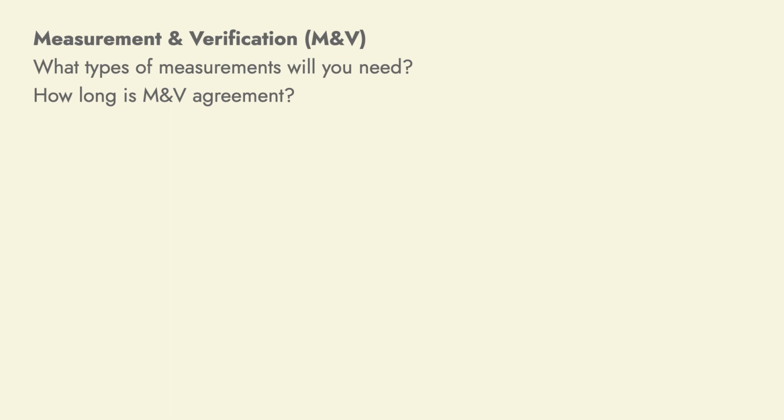Also, how long is that measurement and verification contract? Is it only for a year post-construction, or is it for more than that? 3, 5 years, 20 years, which is not uncommon for things like government buildings that have to guarantee that they are getting the savings that they were promised for a long period of time. Most clients, though, only really need to verify their savings for a couple of years post-construction, because you have gone in, you've already improved their building.